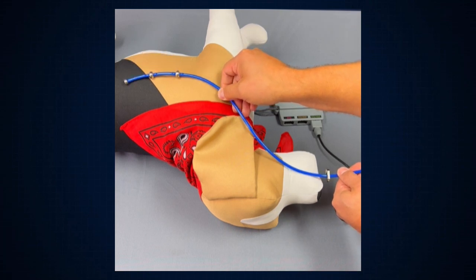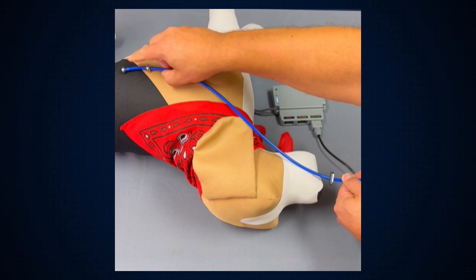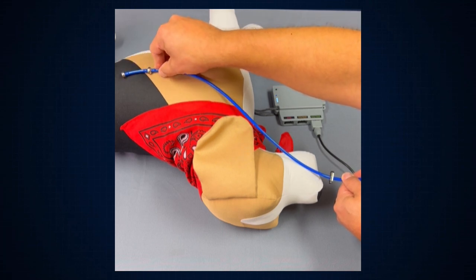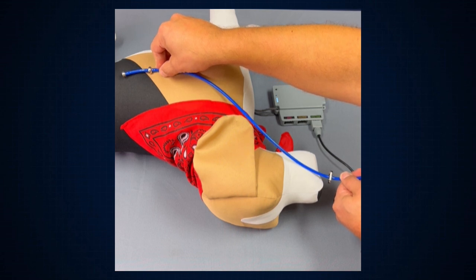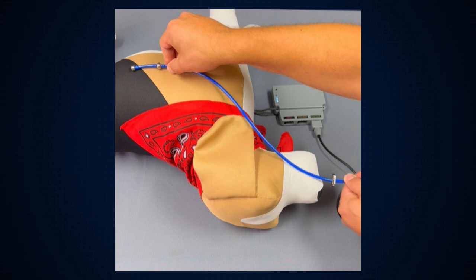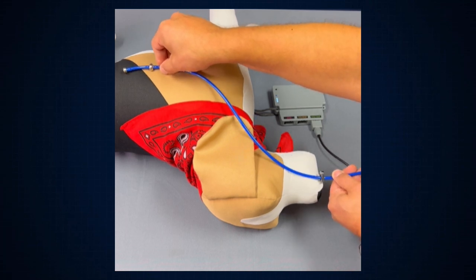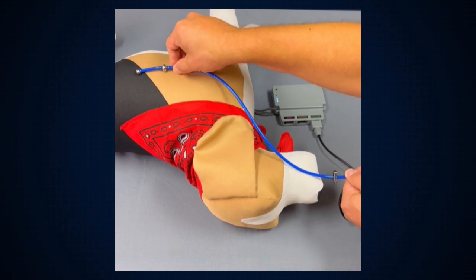And at that point, you're going to get beautiful ECGs as well. There is a temperature sensor built into the tip end of the probe. That is going to give you core body temperature. If you start to lose ECG signal at any time during the procedure, just simply pull the probe in and out of the esophagus, just back and forth about a quarter inch or so.